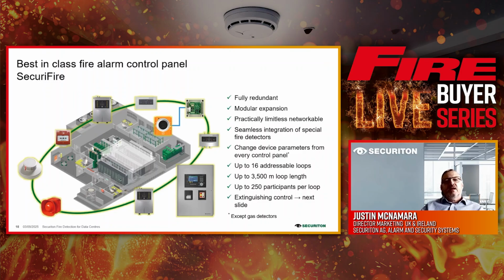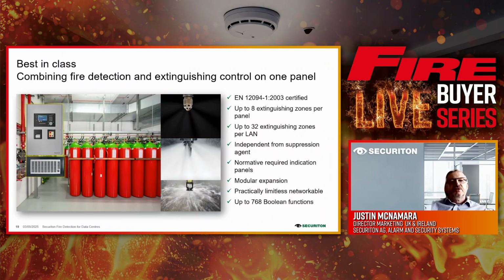Each of those loops can be up to 3.5 kilometers in length. If we add extinguishing modules to our panel, we can provide up to 8 extinguishing zones per panel, up to 32 extinguishing zones in total. And if you read down the list, we can have up to 768 Boolean functions - for those versed in the technology, that means we can provide cause and effect on a limitless basis with AND, OR, etc. functions, allowing us to fine-tune the cause and effect for all devices across an entire site.